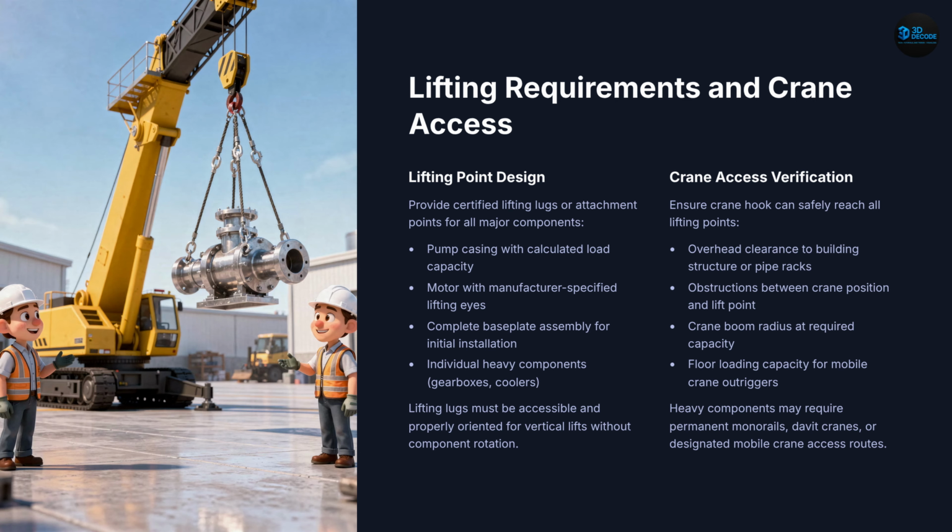Next, lifting requirements and crane access. Now let's talk about heavy lifting engineering. Because pumps, motors, gearboxes, and coolers are extremely heavy industrial components. And if lifting isn't planned correctly from the beginning, future maintenance becomes dangerous and expensive. Every major component requires proper certified lifting points, not temporary improvisation, not chains wrapped around piping, proper engineered lifting lugs. And these lifting points must support calculated loads safely.